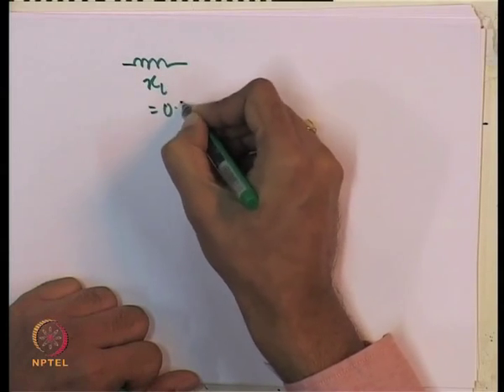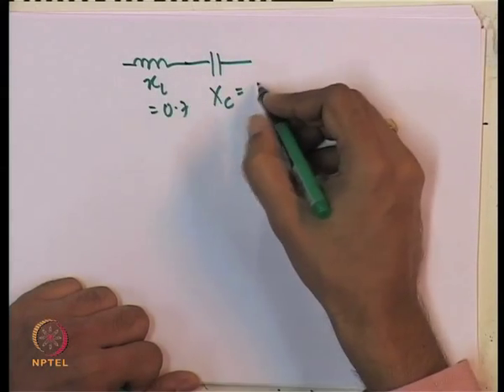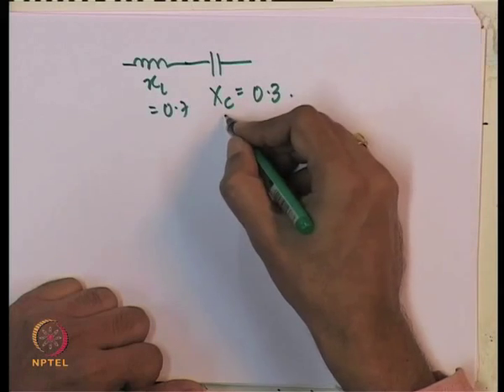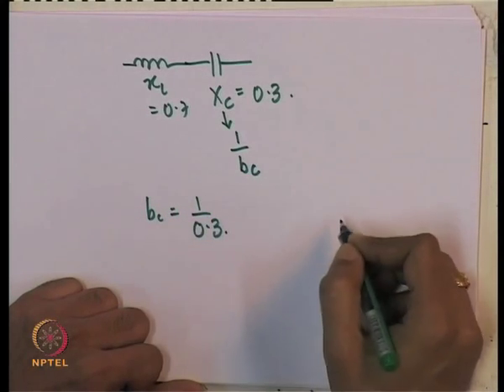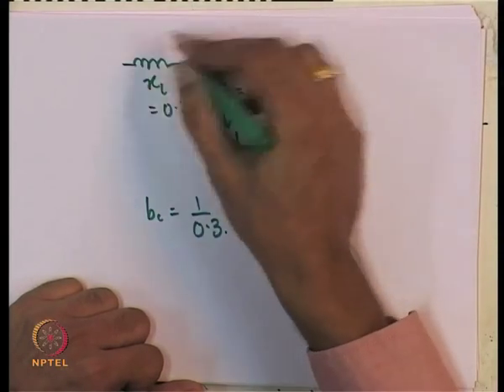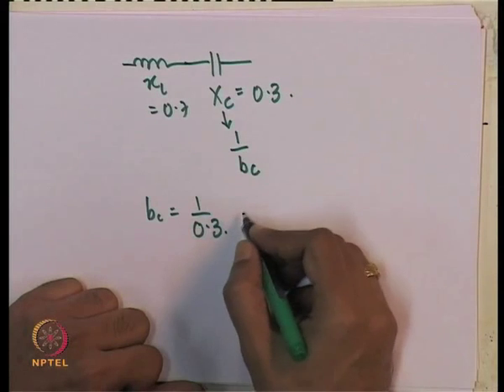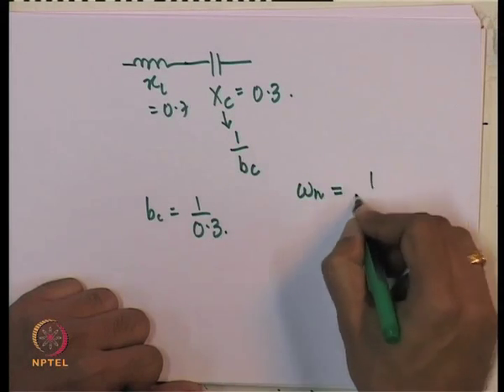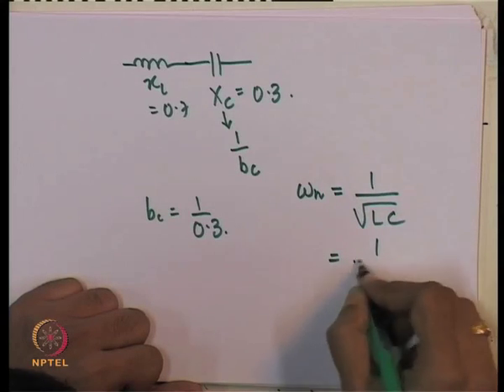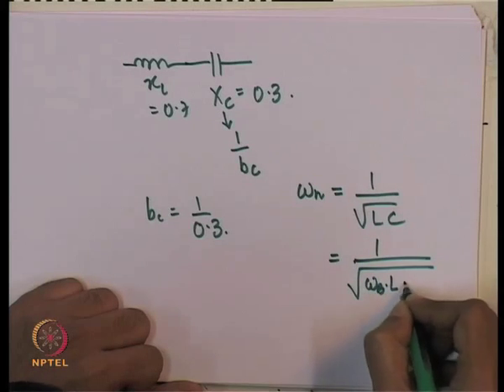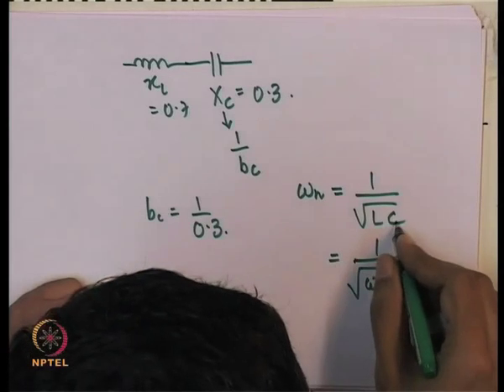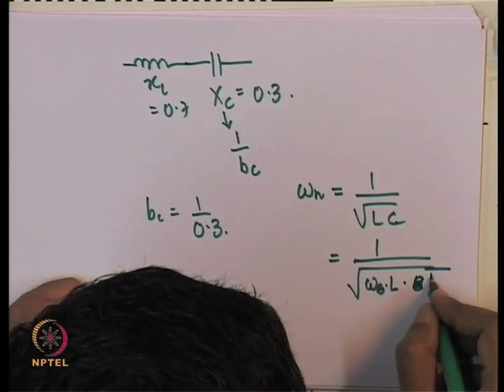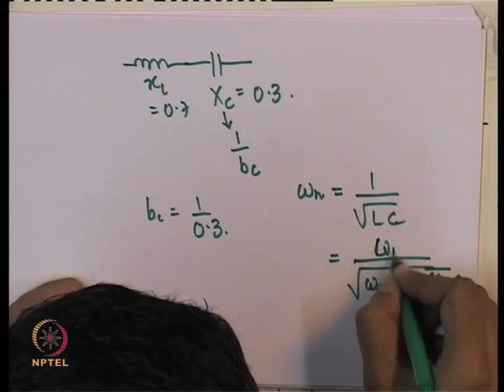In this network, x_L equals 0.7 and x_C equals 0.3 in each phase, so b_C equals 1/0.3. If you look at just this phase in isolation, the natural frequency is 1/sqrt(LC). This is equivalent to omega_B divided by sqrt(x_L * b_C) in per-unit terms — and the natural frequency is the same whether you express x_L and b_C in per unit or actual values.